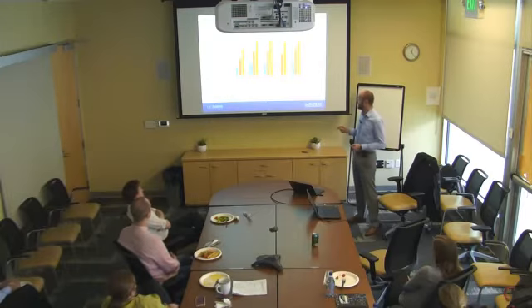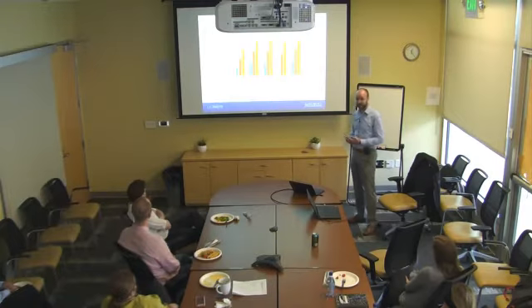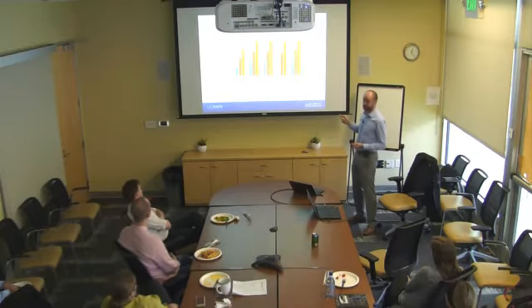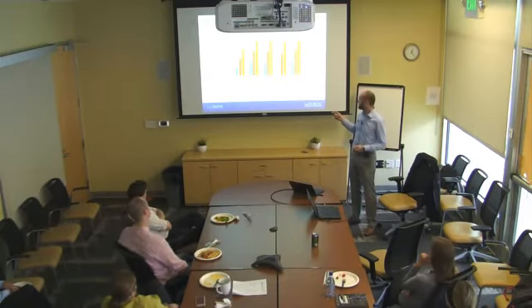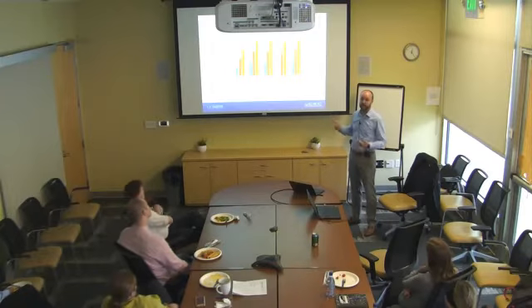So here's some statistics on the error. Basically, the average error was generally around 50%, so you'd actually use 50% more than what the 10-day average baseline predicted you were going to use. It went as high as 76%, so it was a significant error. The only one that ever got close was the water-cooled constant speed chiller, and that was only the minimum - there were times when it almost predicted correctly. That's largely because a water-cooled constant speed chiller is more dependent on wet bulb temperature than really anything else.